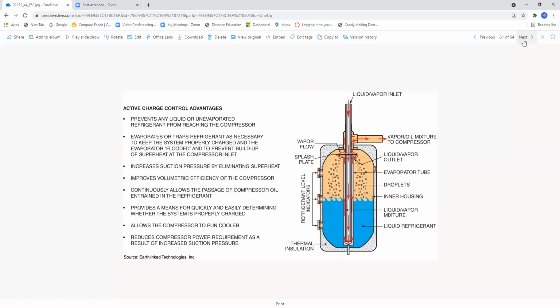Okay, the next page, page 1353, is basically an active charge control system. The advantages are that it prevents liquid or unevaporated refrigerant from reaching the compressor. Remember, compressors are not designed to pump liquid refrigerant. It evaporates or traps refrigerant as necessary to keep the system properly charged and balanced in the evaporator. It's a flooded type to prevent buildup of superheat at the compressor inlet. It increases suction pressure by eliminating superheat. Interesting. It improves the volumetric efficiency of the compressor.